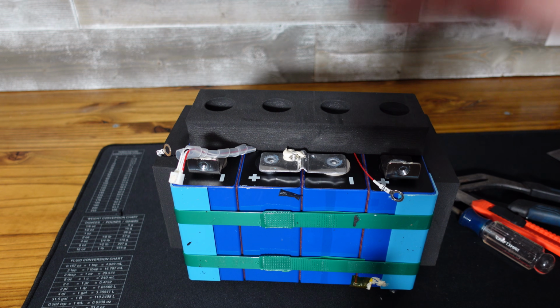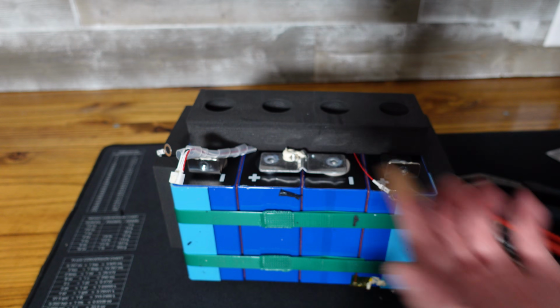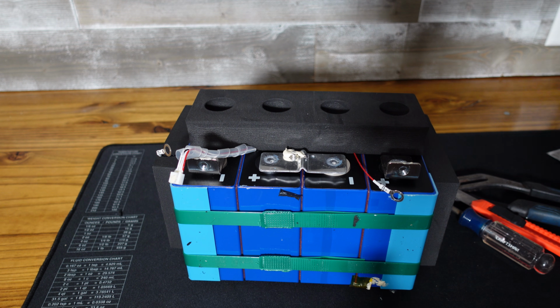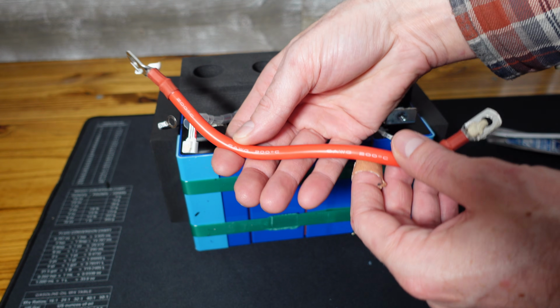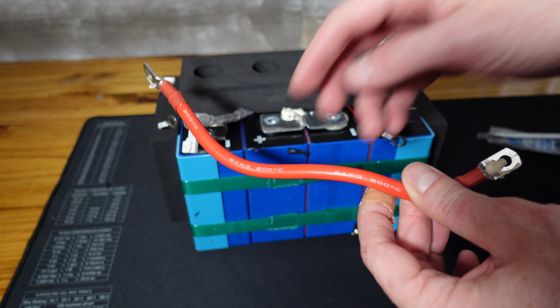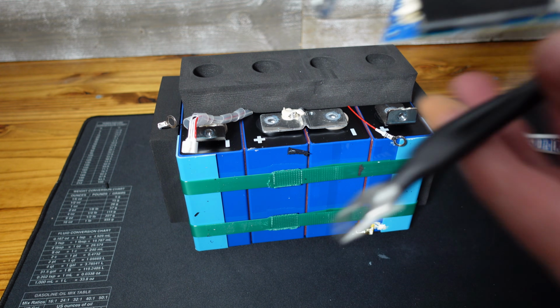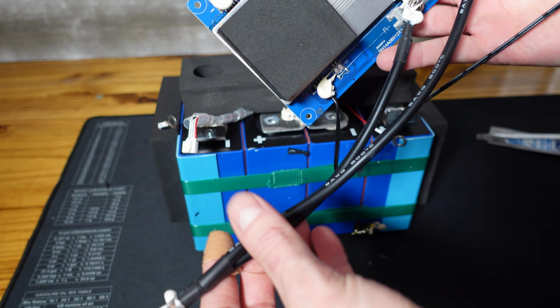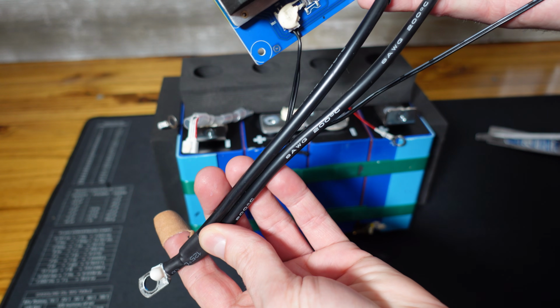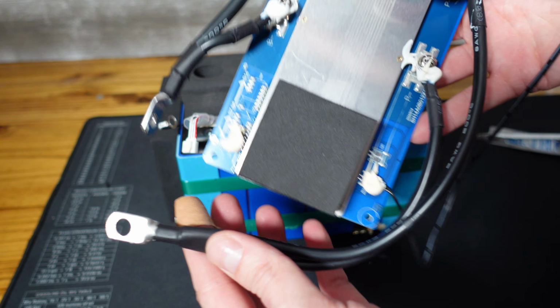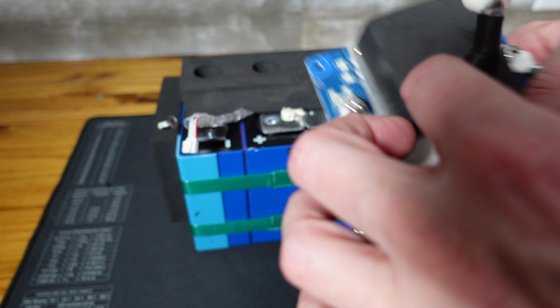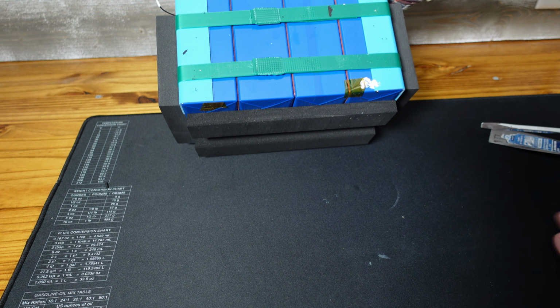All right, a little bit of pounding and one injury later and the battery is out. So let's take a look at what we got here. Our positive conductor is a piece of number 6 silicone insulated wiring, 200 degrees Celsius insulation rating. The negative terminals on the BMS are a pair of number 8 gauge silicone insulated wires. We'll take a look at the BMS here a little bit later. I got that white stuff on my brand new work mat.